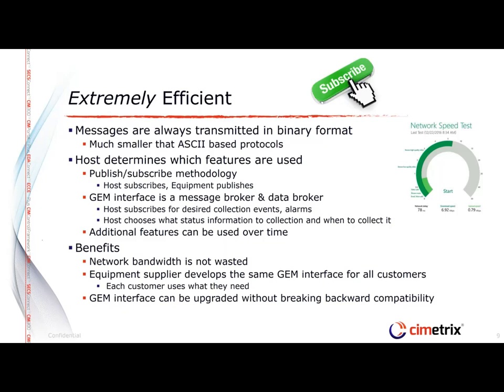GEM also uses a publish-subscribe methodology for data collection. In order for data to be published to the host, the host does need to subscribe. Each GEM interface is a message broker and a data broker residing on the equipment, and that's what allows this publish-subscribe to work so well. A lot of new standards have message brokers, but they are off of the equipment, so you end up flooding the factory networks with data that nobody is even subscribing to. GEM doesn't have that problem and makes very efficient use of the network you do have.